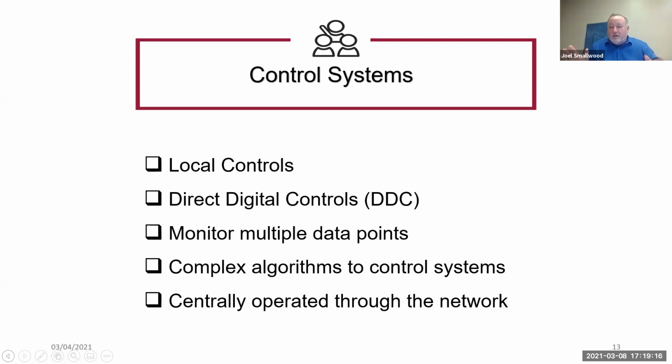It's just one of the major pieces of data that they rely on. And if that pressure drops, the fans inside these units speed up, because it's assuming that it's not delivering the proper volume of air to spaces because there's no pressure. So it continues to turn up the speed on these fans to build that pressure. And then as the pressure gets too high, it'll slow things down a little bit. So that's one of the big data points that comes into this.